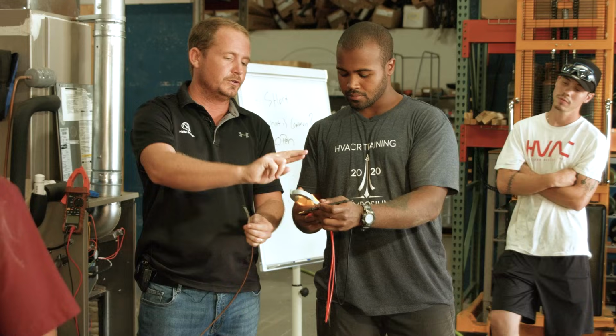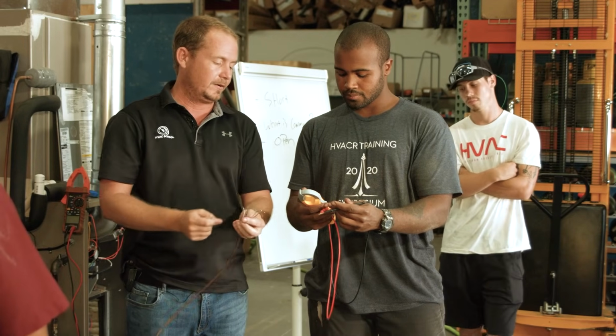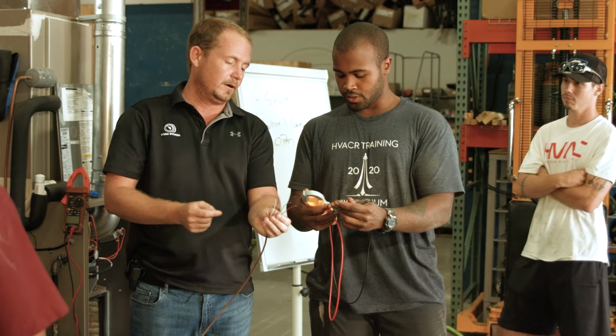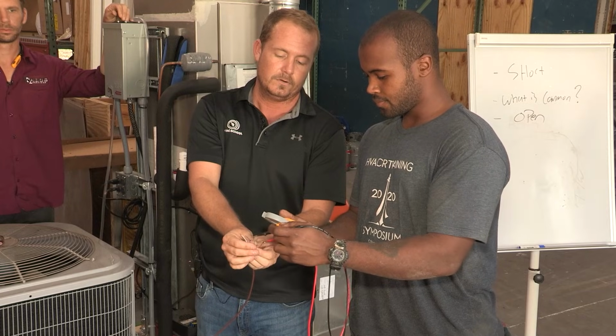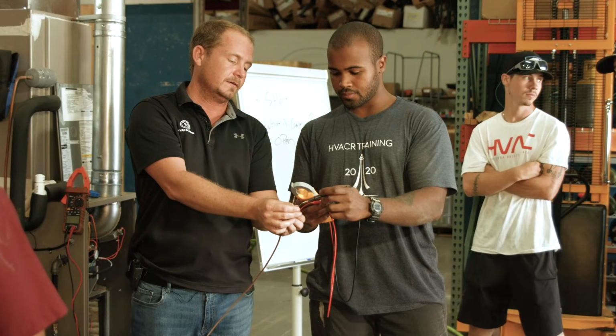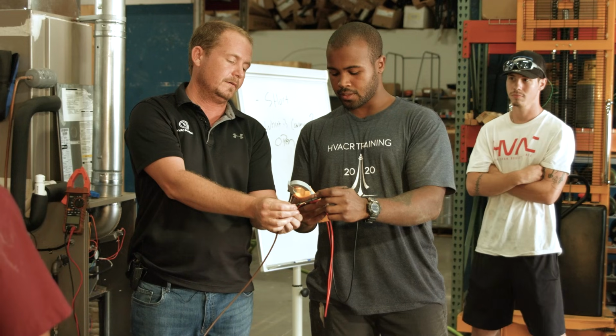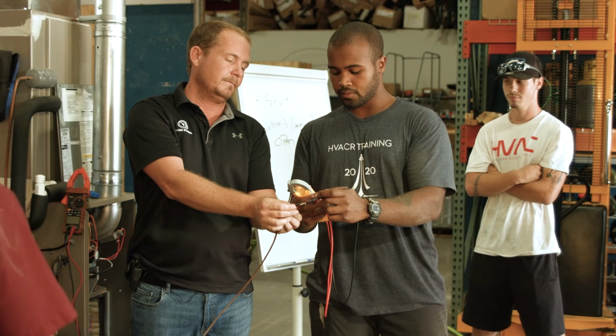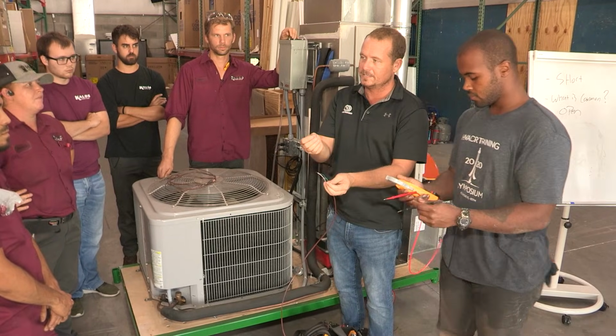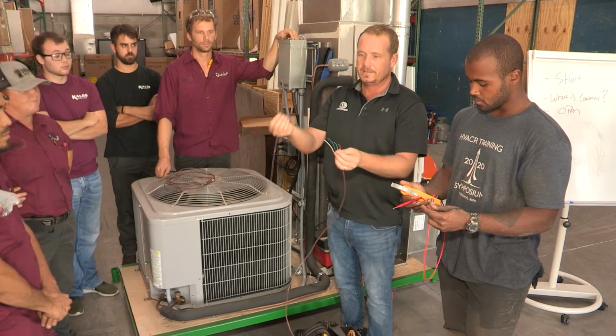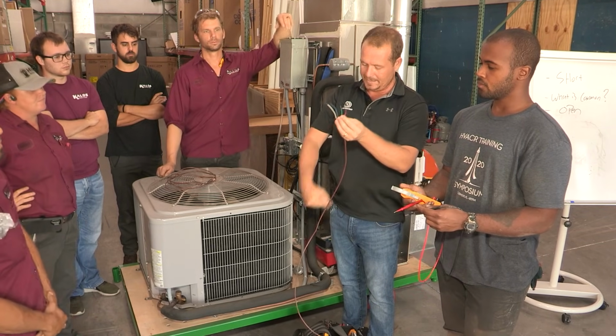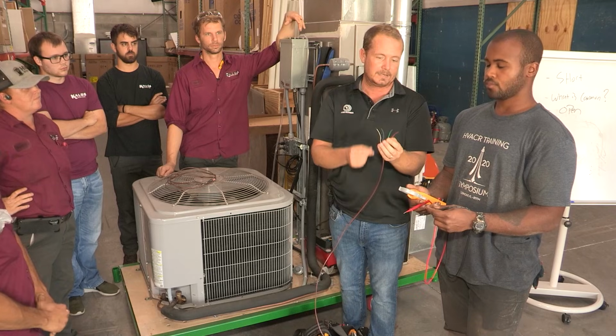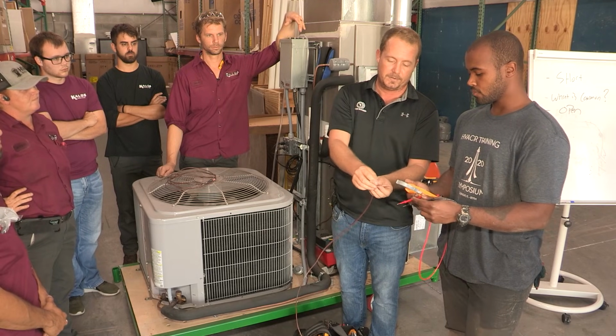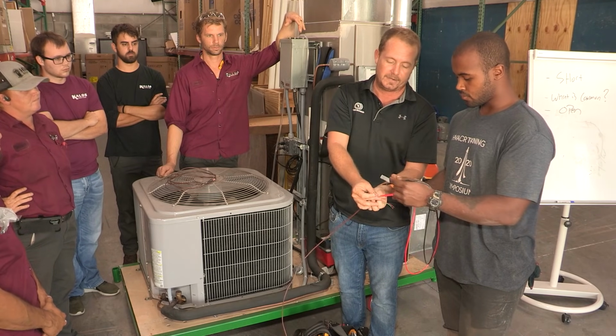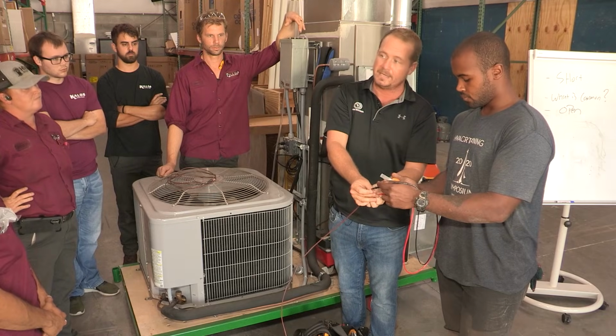Connect the two meter leads together — what are we measuring? Zero, right? Now connect these two wires — what are we measuring? 0.4, so a bit higher resistance, but essentially the same. That means these wires are completely intact, and we can measure all of them together, like blue and white, since they're connected on the other end.